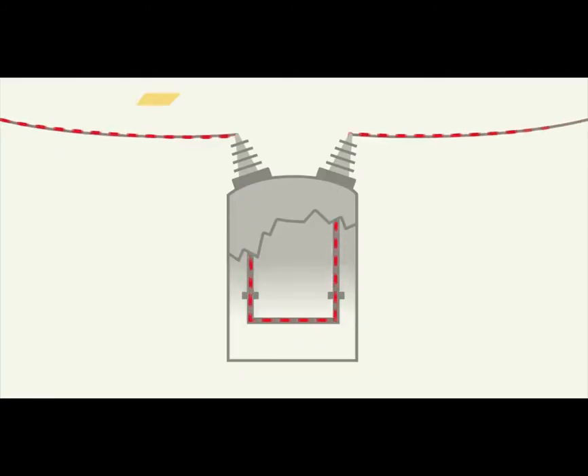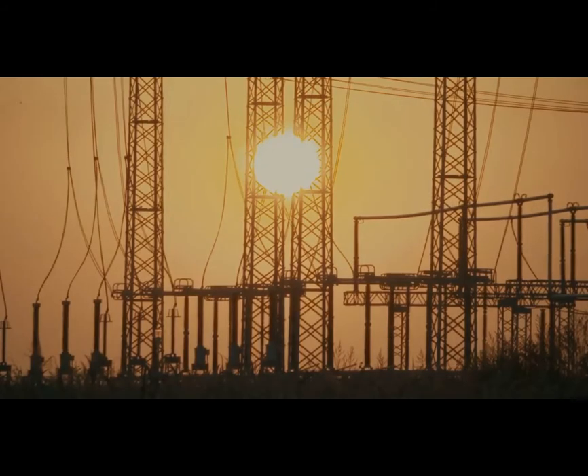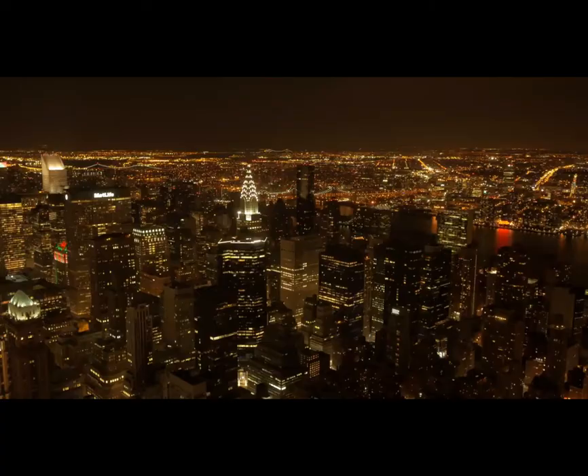Many faults are temporary, like lightning strikes or swaying tree branches. A special kind of circuit breaker called a recloser can interrupt current for a short period of time and re-energize the line to test if the fault has cleared. Reclosers usually trip and re-close a few times depending on their programming before deciding that a fault is permanent and locking out. If electricity demand on the grid gets so high that it can't be met by the utility, substations may also be used to shed load — rolling blackouts lower total electrical demand to avoid bigger failures.